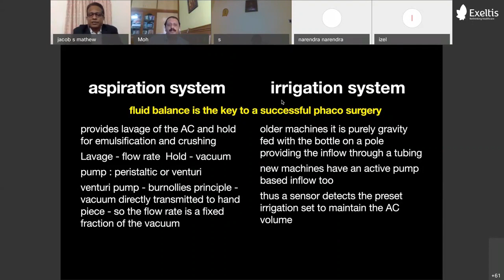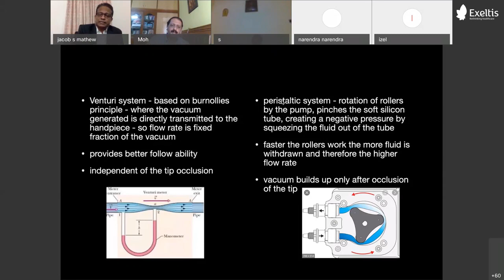So this is Bernoulli's principle that you are seeing first on the left-hand side. The Venturi provides better followability. It happens a lot faster. The flow rate is very high, and it comes very fast. And your procedure is done in a more efficient way, and it's independent of tip occlusion, whereas in a peristaltic pump you need to occlude the tip, and only then the vacuum starts building up. So you can see how the peristaltic pump works on the right hand side of the slide.